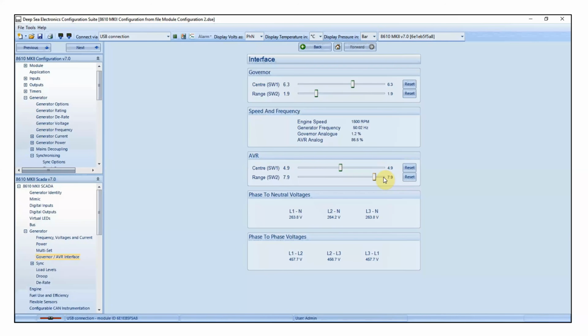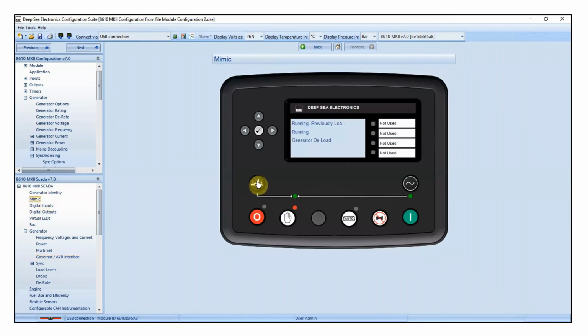So as I'm getting closer and closer in this example to the 80%, I'm just slowing my clicks down, as it were, just to make it easier and not overshoot that 80% I'm trying to achieve. So here you can see we've got a very good value of nearly exactly 80%. Very nice. So all I'm going to do now is go back to the Mimic page, open the generator breaker, and stop the generator.